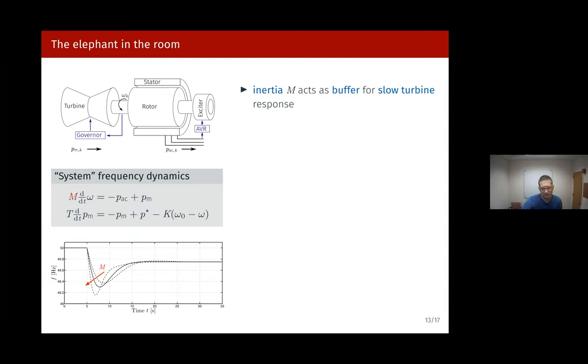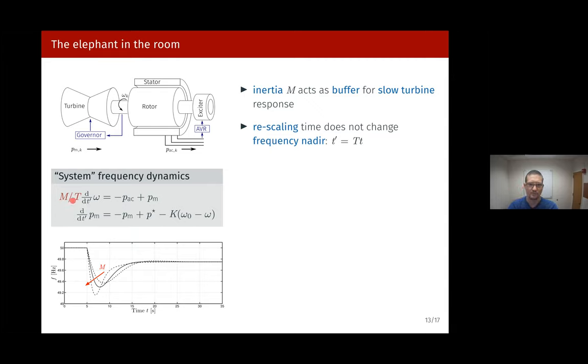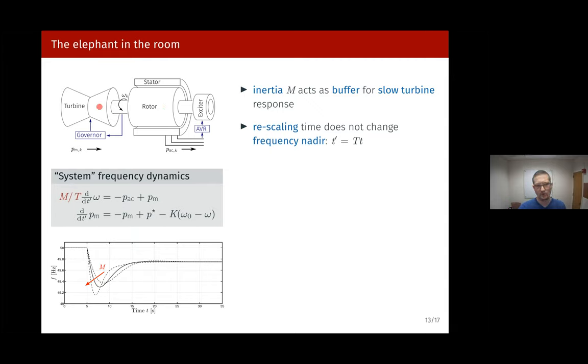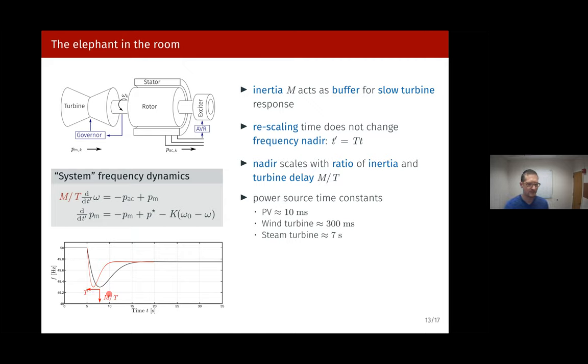The turbine time constant T controls how fast you reach the frequency nadir, while the frequency nadir itself basically scales according to the ratio between inertia and turbine time constant. The turbine time constant moves the nadir left and right in time, while the ratio shifts it up and down in magnitude. Now, if you consider going to a system with more renewables interfaced by power electronics, the time constants modeling these devices are orders of magnitude smaller than a traditional turbine governor — a steam turbine might have T of seven seconds, photovoltaics around 10 milliseconds, and wind turbines maybe 300 milliseconds. So as we go to faster and faster power sources, we need less and less of an inertia buffer.